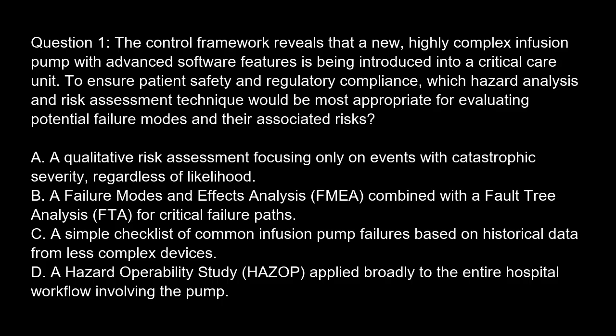Option A. A qualitative risk assessment focusing only on events with catastrophic severity, regardless of likelihood. Option B. A failure modes and effects analysis (FMEA) combined with a fault tree analysis (FTA) for critical failure paths. Option C. A simple checklist of common infusion pump failures based on historical data from less complex devices. Option D. A hazard operability study (HAZOP) applied broadly to the entire hospital workflow involving the pump.